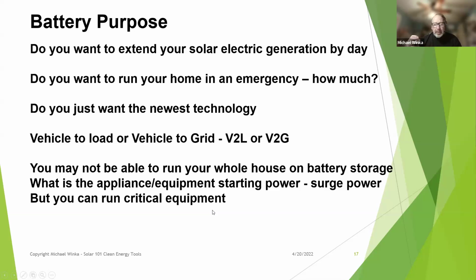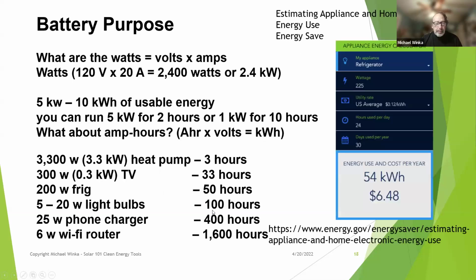You also got to think about power surges. So your heat pump comes on, it has a surge in the beginning. Instead of needing 3,000 watts, it may need 5,000 watts to turn on. You have to calculate that if you're thinking about running all your critical loads when the power goes out.